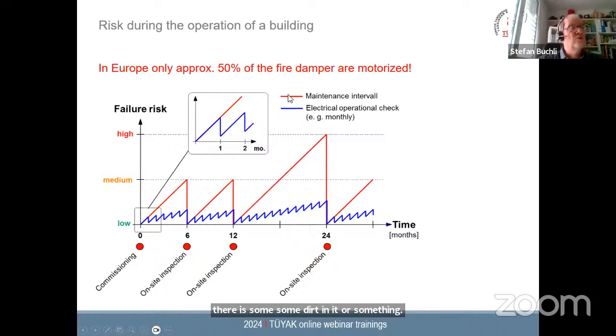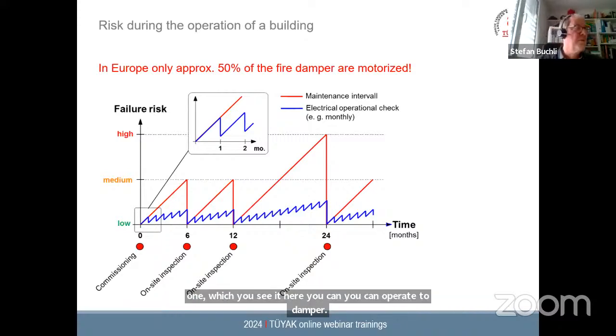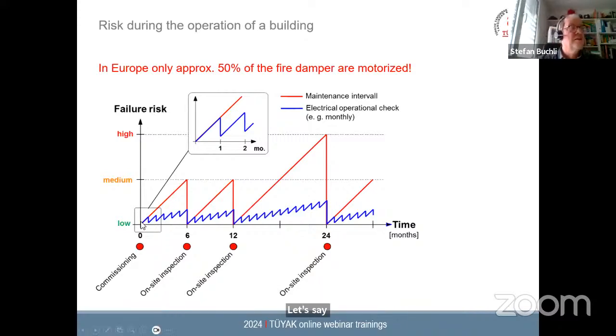And on the motorized side, you have the advantage. You see it here. You can operate the damper, let's say once a week, once a month, whatever. And then you always get a feedback. Okay, damper is open, damper is closed again, or open again, and you have this feedback, and you know, okay, the damper is still moving. Actuator is okay. Damper is moving. So the risk is a little bit differently.